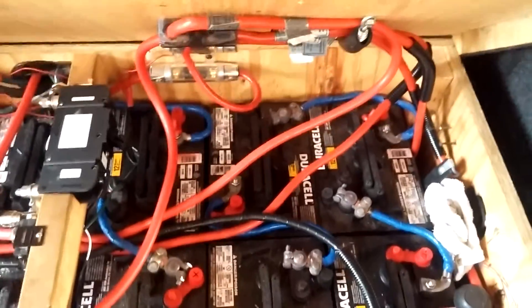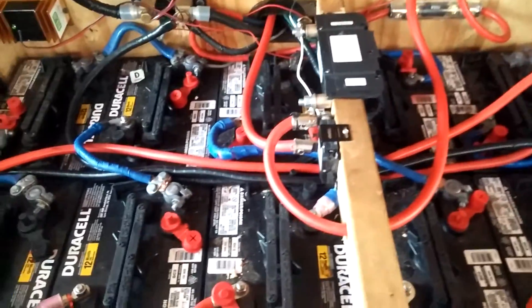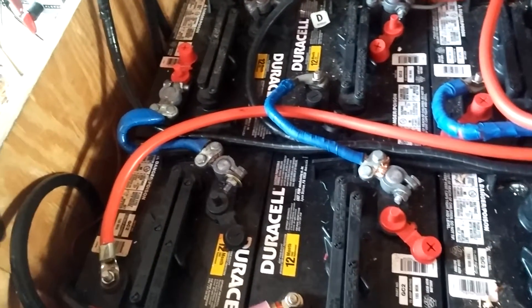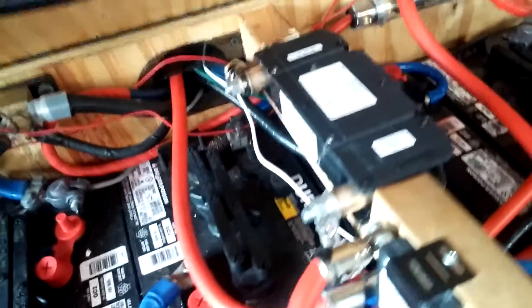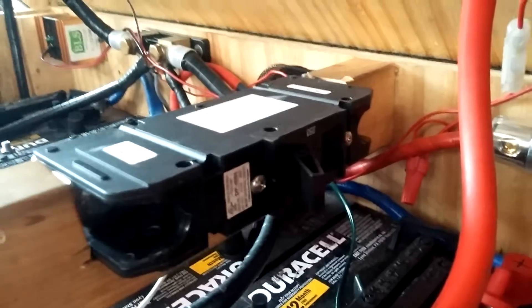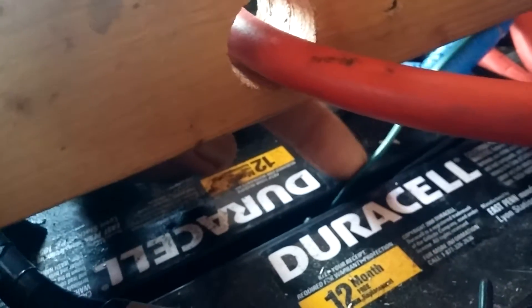Let me take you on a trip to my battery bank. I've got 12 deep cycle 6-volt golf cart batteries here — three sets of four batteries wired in series and then in parallel together, all coming to this point. This is where I installed the breaker for the AIMS inverter, which works out great. There's also a temperature sensor in here for the Ames and another temperature sensor for the Flexmax 80.